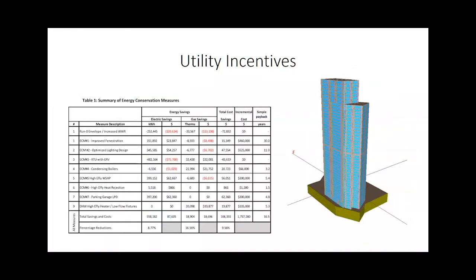So for the RESI project in Boston, we looked at about 9 different ECMs: improved windows, the solar heat gain thing I talked about earlier, reduced lighting power density, better ERVs on the RTUs, condensing boilers, the high efficiency water source heat pumps we talked about earlier, high efficiency heat rejection, reduced lighting power density in the parking garage, and some high efficiency domestic hot water heaters and low flow fixtures.